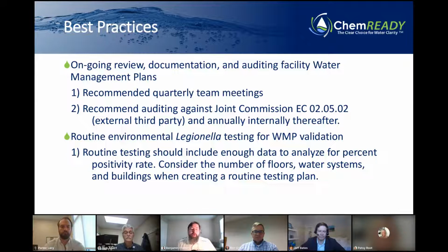My favorite phrase as a water treater is, it depends. It depends on your facility, your building, and how effectively your water management plan is being implemented. But in general, best practice is that you should generate enough data to analyze the percent positivity rate that Ron was just speaking about. If you're only taking one test a year from one location, that's not enough data to analyze the risk of Legionella in your system. Things to consider are the number of floors, water systems, and buildings, and you want sampling from each with enough data to take real action based on the results. That's the best practice for how often to test for Legionella.